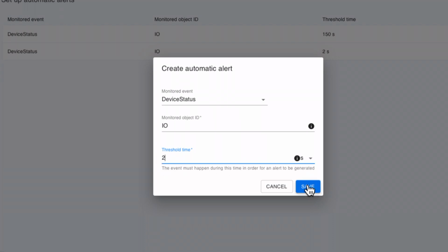If an error occurs for only 1 second, maybe it was one-off interference. This interference, in the case of the example we are doing, would not make sense, because they are the inputs and outputs integrated in Adquio. It would be more logical with an external device, which we selected here, where between it and Adquio there is a bus susceptible to receiving interference, right?